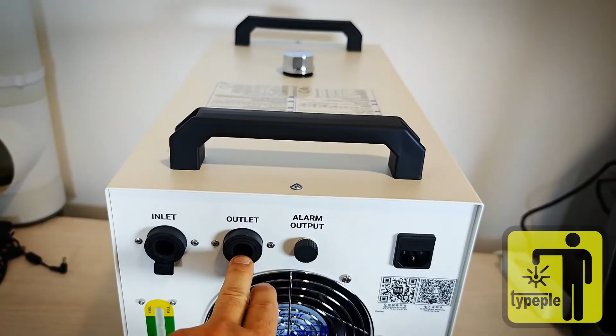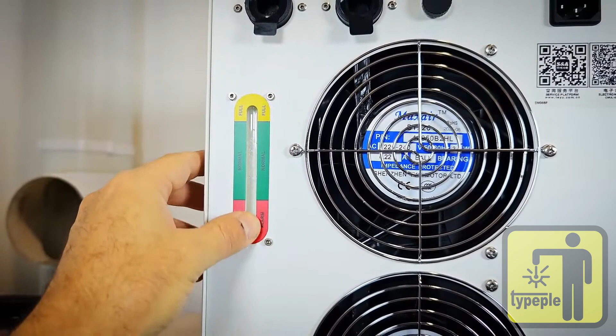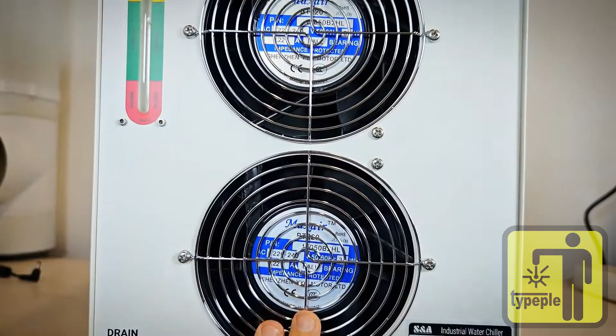The GX16 by 3 connector itself, 220 volt power. 2 QR codes for service and the manual, an indicator tube that just runs through here. Actually, there's more. There's nothing here. The fans, there are two of them here, 220 to 240 volts, 0.22 amps, ball bearings. Well, basically, it seems pretty good. It says there's some special protection here, so it's the same on both. Information, drain valve, serial number, a nice holographic sticker, and the instructions, or industrial water chiller. A little manual on how to fill it, top it off, and all the other details.